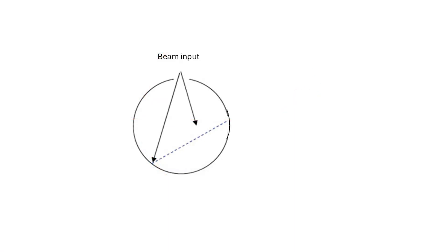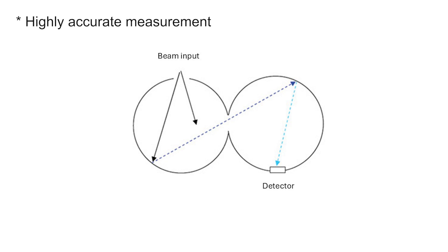The Ophir 3AIS uses a neat trick particularly suited to small spheres where the light from one sphere is fed into a second sphere in tandem. This helps ensure highly accurate measurements for both collimated and diverging beams.